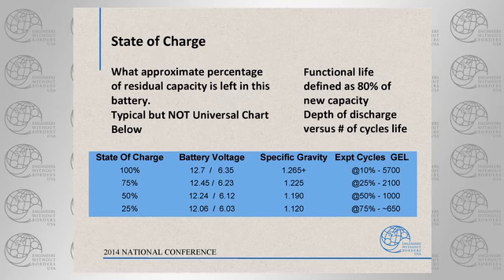Expected number of cycles. Now, this is in particular for a particular gel cell product. If you use the battery and only use 10% of its rated capacity, this manufacturer says you get 5,700 discharge charge cycles. Okay, if we do a discharge charge cycle once a day, that's a pretty long life. That's a great battery for that use. But that means you're buying an awful lot of batteries if you're only using 10% of the rated capacity.